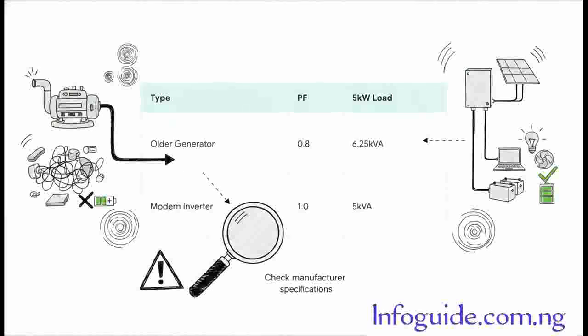That blew my mind a bit, because it perfectly illustrates why assuming a 1-to-1 ratio across the board is so incredibly dangerous. If you buy a 5 kVA machine with a 0.8 power factor, expecting it to run 5,000 watts of your gear, you are absolutely going to fall short and overload your system. You have got to check the manufacturer specs every single time.